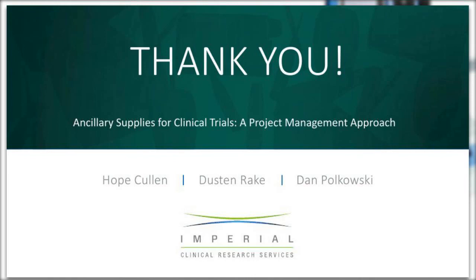When you supply large items like centrifuges and refrigerators, do you also deal with maintenance on site? At this time, what we would do is we would look at contracting, hopefully locally if we can, or as close to the site as possible, and have somebody perform those calibrations or any kind of services or repairs if it's a particularly large item. The smaller ones that can be shipped, it would actually be better to do what we call a repair replace, or basically what that would mean is I would send you a working unit that's already calibrated and maintained, and you would send the other one back to me, and then we would just do a round robin like that.